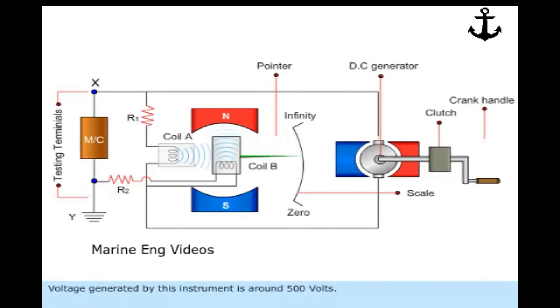Voltage generated by this instrument is around 500 volts. Meggers are available to generate 1000 volts, 2500 volts, and 5000 volts also. High voltage meggers are either motor operated or power operated.